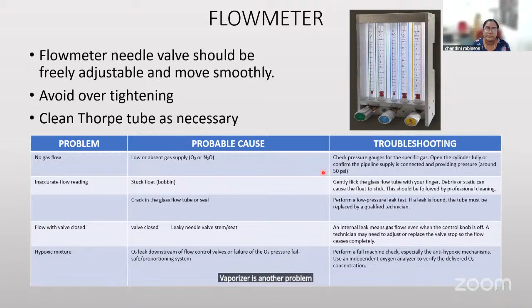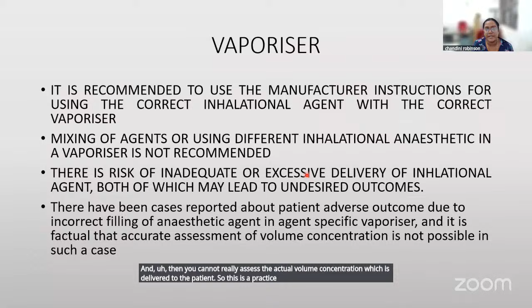The vaporizer is another problem which we may face, because with the Boyle's machine, primarily the Goldman vaporizer is available, but sometimes it is retrofitted with Tec vaporizers. Tec vaporizers are agent specific. The ideal way would be to ensure that we use the specific agent in the specific vaporizer. Mixing of agents is not recommended, and there is a risk of inadequate or excessive delivery of the inhalational agent, which may lead to undesired outcomes. There have been reported cases of patient adverse outcomes due to incorrect filling of anesthetic agents, and then you cannot really assess the actual volume concentration which is delivered to the patient. So this is a practice which is ideally to be avoided.